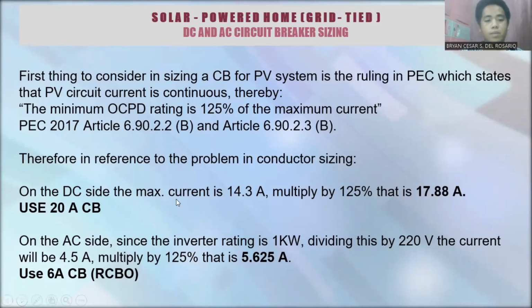On the DC side of the MPPT, pag titingnan natin doon sa spec sa kaninang kinumpit natin, yung current niya is 14.3. So multiply lang natin sa sabi dito sa rule, ay dito sa sinabi ko kanina na 125%. So pag multiply natin, ang lalabas doon is 17.88 ampere. Since wala ulit na gantong eksaktong circuit breaker, gagamit na lang tayo ng 20 ampere circuit breaker.